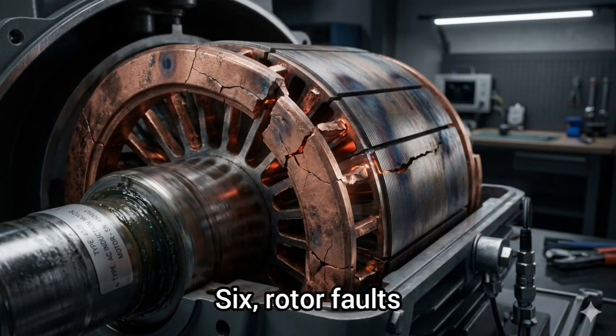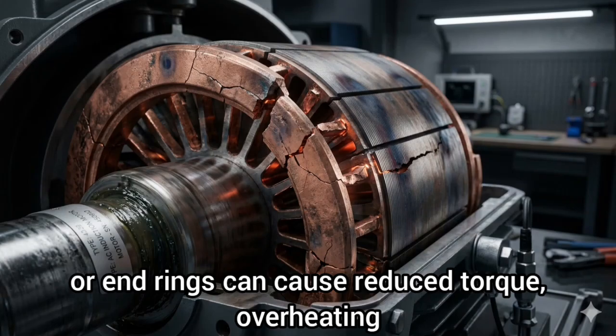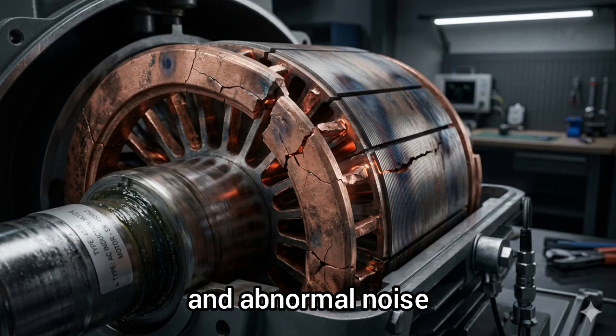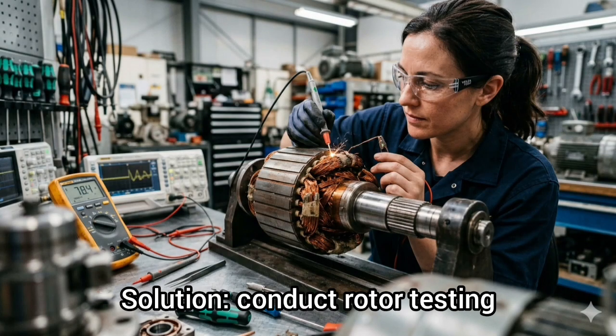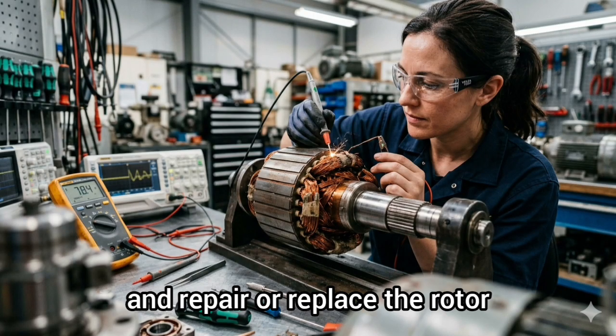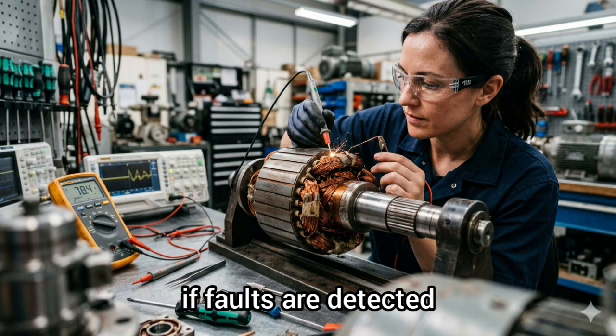6. Rotor faults. Broken rotor bars or end rings can cause reduced torque, overheating, and abnormal noise. Solution: conduct rotor testing and repair or replace the rotor if faults are detected.